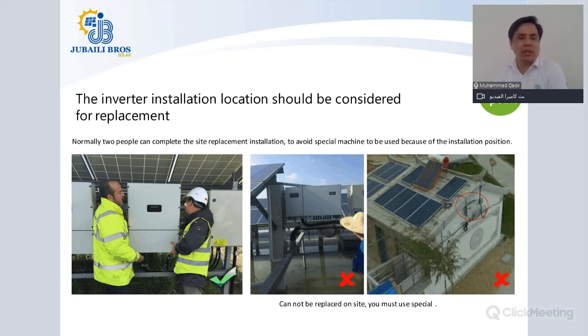The inverter installation location should be considered for replacement. Now, in the long life of a PV system, your inverter might face some malfunctions, and if you have to go and check it, or take it out and dismantle it, it will become very difficult if it is installed at a location which is not easily accessible. Such scenarios can be seen in the right two pictures.